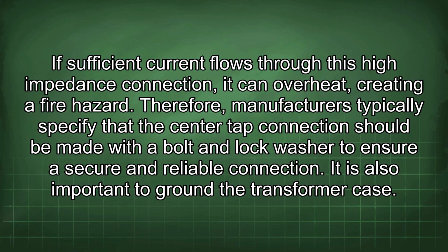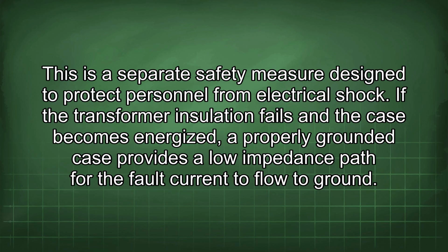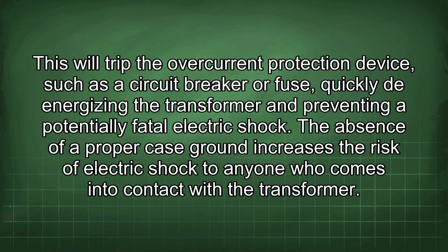It is also important to ground the transformer case. This is a separate safety measure designed to protect personnel from electrical shock. If the transformer insulation fails and the case becomes energized, a properly grounded case provides a low impedance path for the fault current to flow to ground. This will trip the overcurrent protection device, such as a circuit breaker or fuse, quickly de-energizing the transformer and preventing a potentially fatal electric shock. The absence of a proper case ground increases the risk of electric shock to anyone who comes into contact with the transformer.